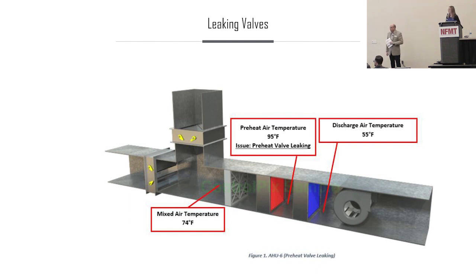Question? We typically try to advocate for percent open. Oh, yes. For the controls techs that we work with, if they try to argue one way or the other, we usually say, look, we don't really care what you end up doing. If the owner does not care, then we do not care as commissioning agents. However, on your BAS, please put percent valve open or percent valve closed so that there are no questions in the future, because I'm not trying to have two dampers closed off to a running fan. And if it's a new installation, be consistent with the previous installation.